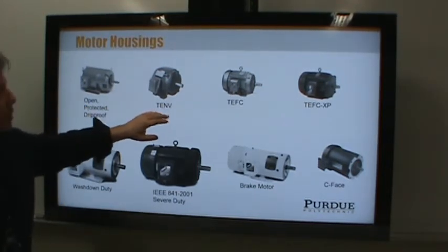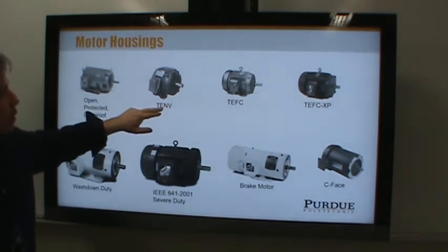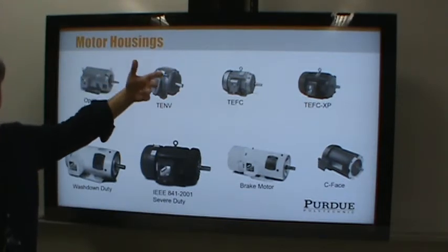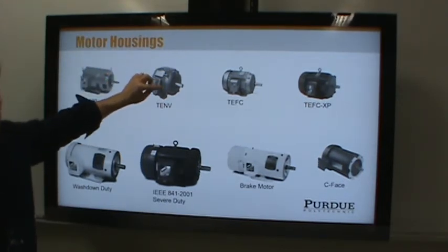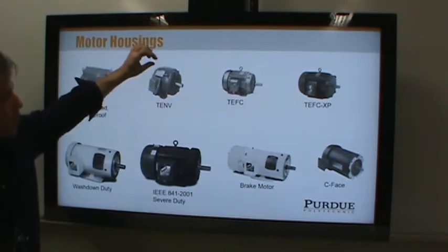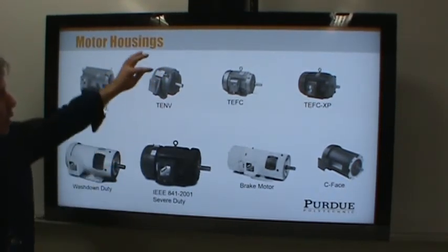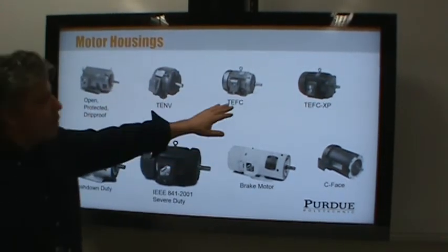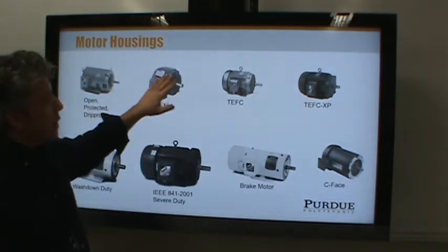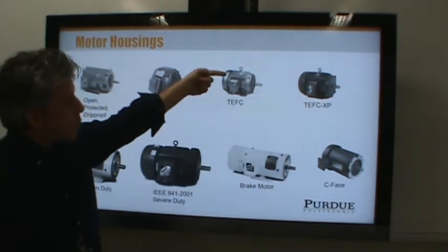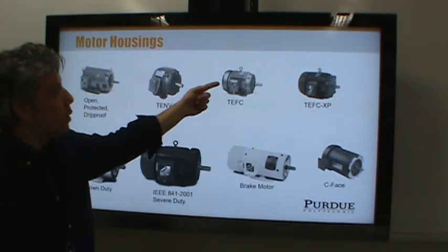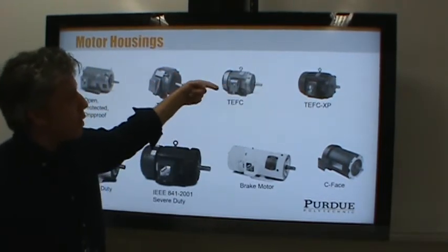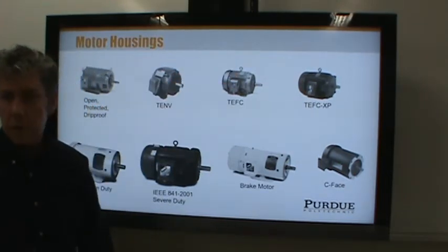There's also TENV — Totally Enclosed Non-Ventilated. There are no holes in this at all. To get the heat out, they include fins so you can transfer heat by conduction and convect it away, preferably by a fan mounted on the motor. The TEFC — Totally Enclosed Fan-Cooled — has a sheet metal shroud on the back covering the fan, which is mounted to the rotor. As the rotor turns it pulls air across the heat exchanger fins.